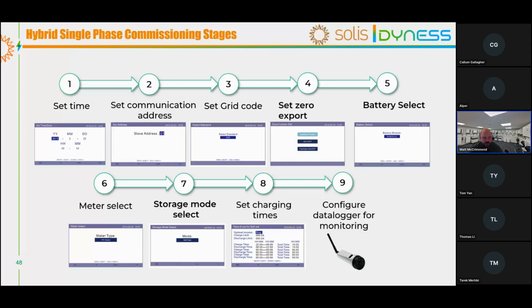You then look at the storage mode select, so that's when we talked about the different storage modes. So we have self-use or feed-in priority. So as I said, 99 times out of 100, or probably 100 out of 100 in the UK, you're going to set it to self-use mode. Once you're in self-use mode, it will then prompt you to set charge times or the time of use. And that's where you can set up 3 charge windows. So the charge windows are based on current, so you always set the charge current and then the time window.